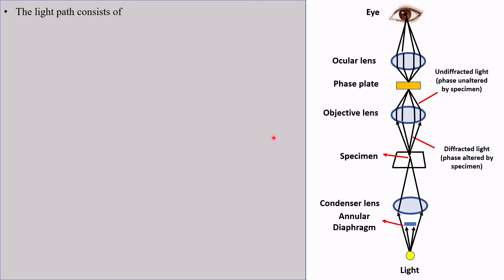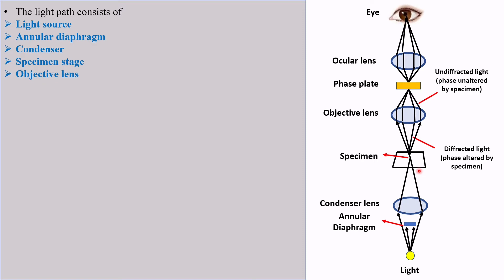The first modification is the annular diaphragm, which is placed in place of the opaque disc. The annular diaphragm is almost the same thing as an opaque disc with a little modification. The major modification in the phase contrast microscope is that a phase plate is placed between the objective and ocular lens. The light path of the phase contrast microscope consists of the light source, annular diaphragm, condenser lens, specimen stage, objective lens, phase plate, and ocular lens.